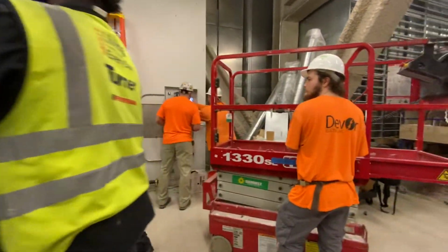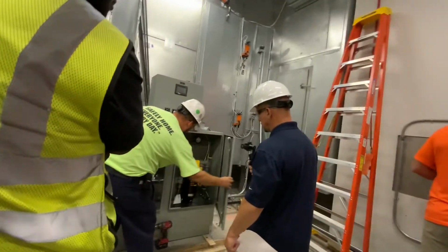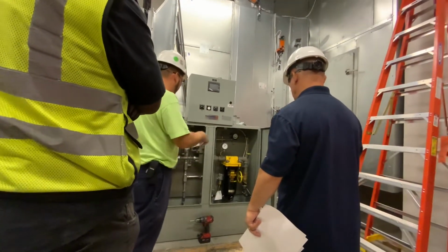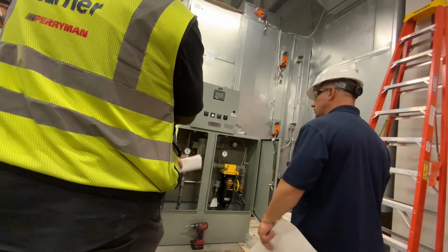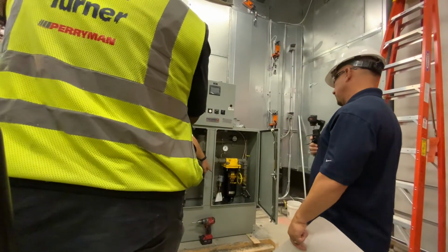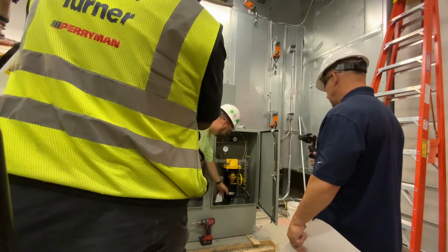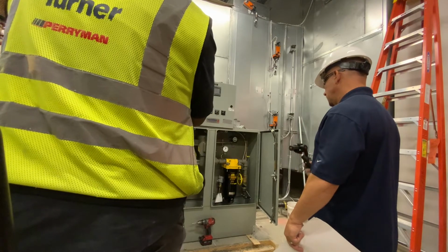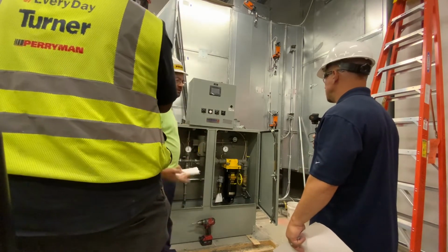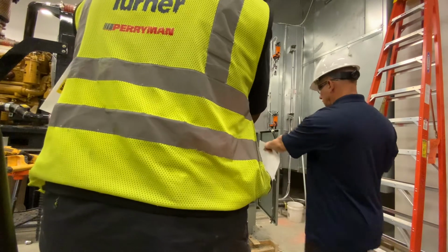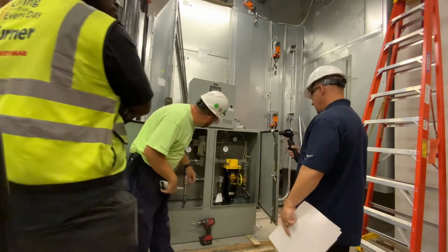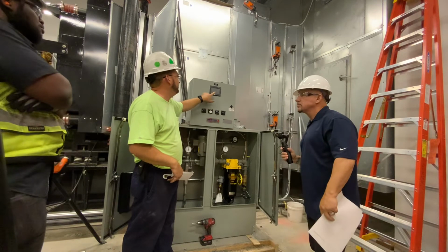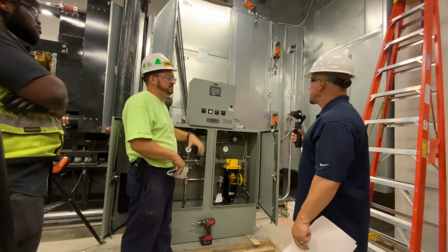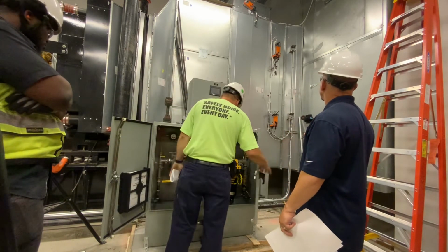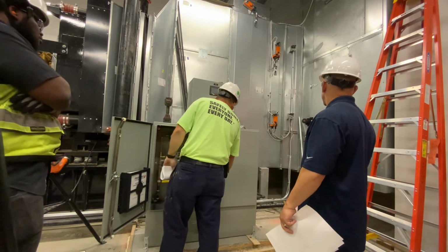That was a filter head - yeah, it's got a big filter there. So this thing just circulates the fuel in there, basically polishes it, keeps it clean. If there's any condensation or water, it's going to pick it up and it'll sit in here where you'll get an alarm. You see the probe down here. It'll tell you basically, on the screen, like water and filter drain or something like that. And then if your filter plugs, it tells you to change your filter. This has got a little PLC in here, so it's got a pretty sophisticated screen on it. Should be pretty easy to figure out, just have somebody come in and explain it.